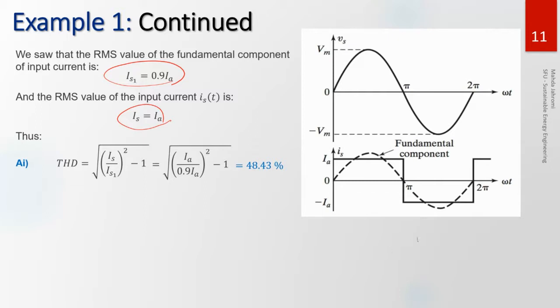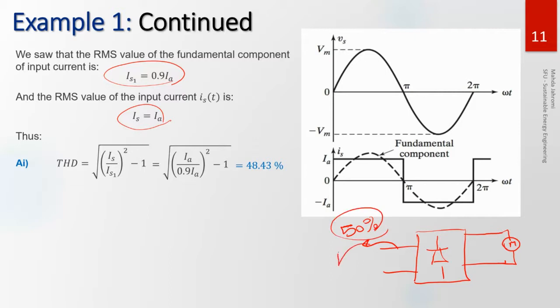That means that if you plug this rectifier into the wall to supply a DC motor, you will get about 50% harmonics back into the grid. By standard, these days you cannot have a THD that is more than 5%. So this is 10 times what you're allowed to put back.